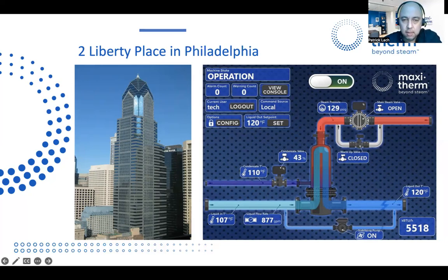Now, with that service tech and everything, if you look at this picture, I want to draw your attention to the temperature set point, which is 120 Fahrenheit, which is the big trend now, to go to a low temperature set point on the hot water loop for building heat. If you look at the temperature return on the bottom left side of the touchscreen, it's 107 Fahrenheit. Now, if you look a little bit higher, the temperature discharge of the condensate is 110. Only 3 Fahrenheit difference with the temperature discharge. So no quencher is needed.